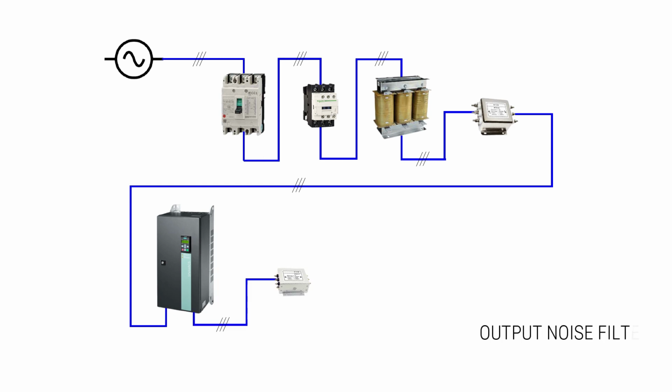Output noise filter or EMI suppression. When used with output noise filter, radiated and conducted emissions may be reduced. Filters protect motors from EMI and voltage transients output from the drive itself. Not required if the motor is inverter rated.